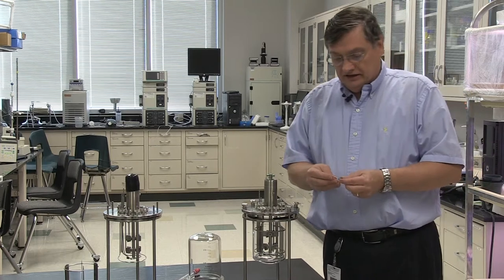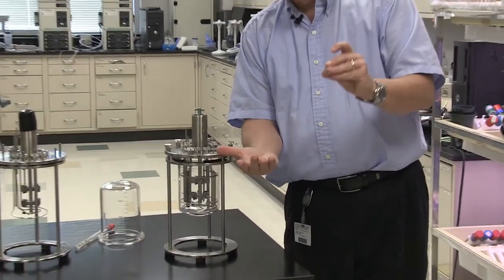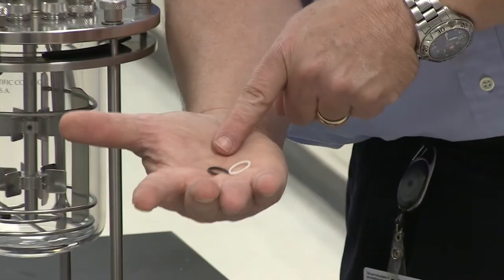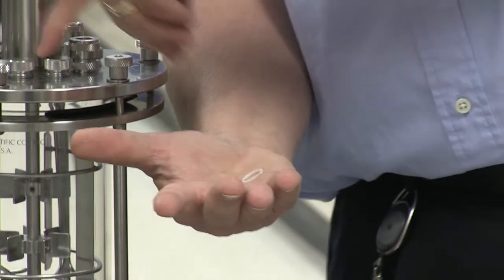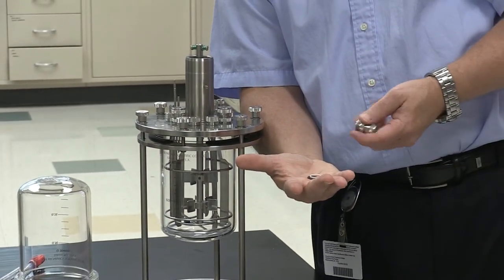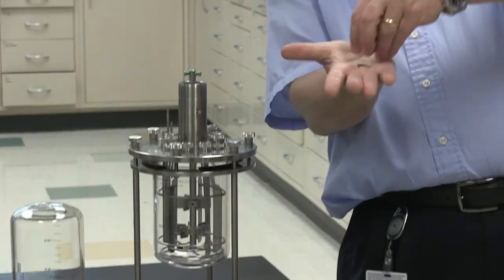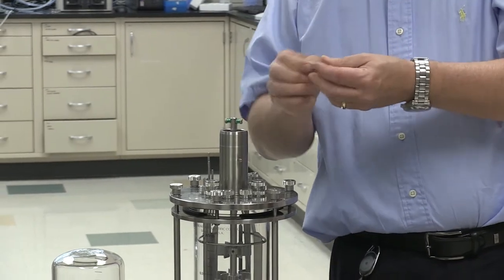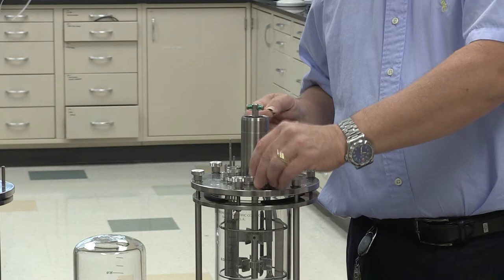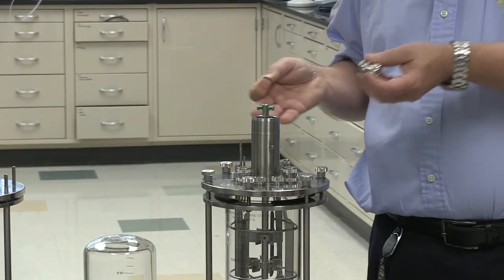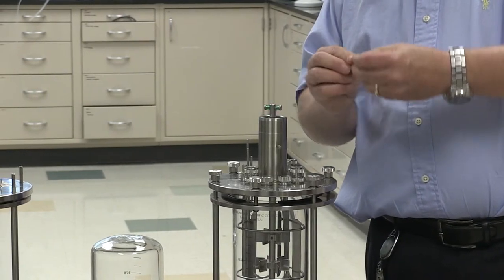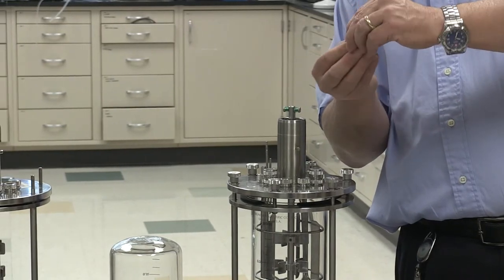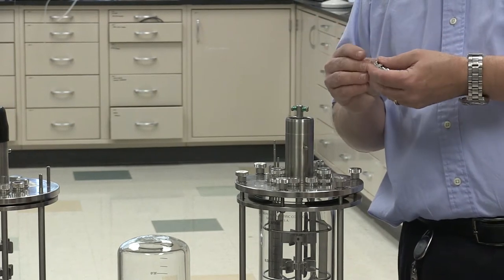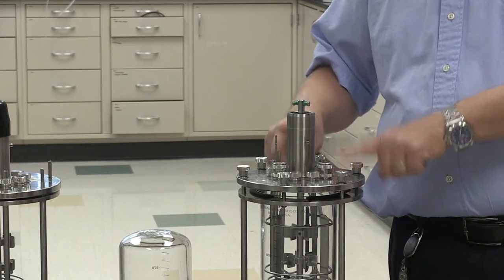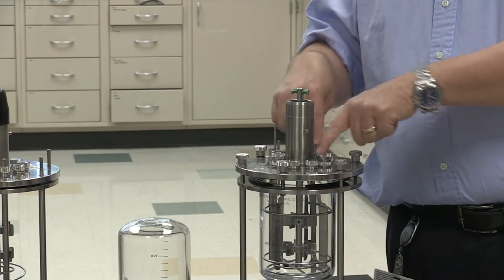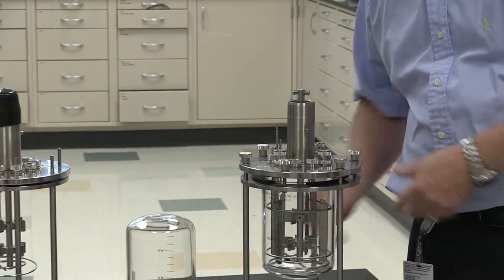You also notice, maybe if I put it against my hand here, you can see it. At the base of the fitting are these two O-rings. There's a Teflon one and a butyl rubber one. Right? And so at the base of each one of these fittings, even the blanks, there are two O-rings. And the Teflon one, as we're looking, goes up, and the butyl rubber one goes down. So this is also a buffer from metal to metal. Now, the metal is both stainless steel. They have the same expansion coefficient, but it's good to have these spacers in here, even so, to keep them from locking up and to have a cushion. So as you're assembling your vessel, it's always a good thing to check all your fittings, before you start putting your probes on, to make sure that each has these two O-rings with it.